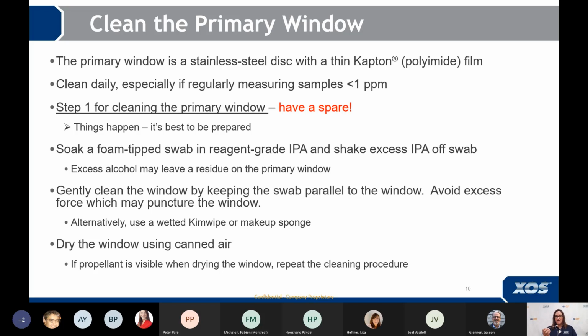And speaking of swabs, we recommend a foam tipped swab here, and we're going to use the reagent grade isopropyl on that. The foam tip swab is better than Q-tips because it's much more gentle and less likely to puncture. And when you squirt it with alcohol, which I'm going to do here because you won't see me doing this later on camera, you squirt the swab and then you want to make sure to shake it off. That excess alcohol may leave a residue on the primary window, so you want to make sure to shake the swab off. And when you clean, it's really important how you hold the swab. If you clean it like this, you will be more likely to break the window. So you want to hold the swab parallel to the window and avoid using excess force.